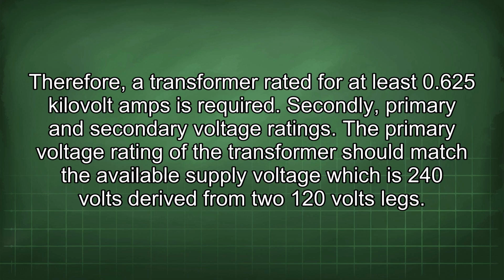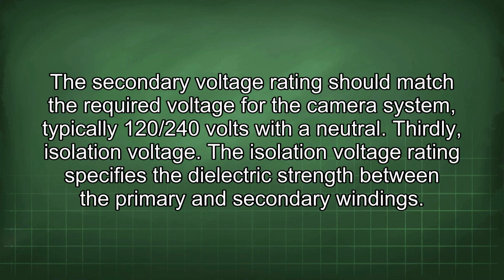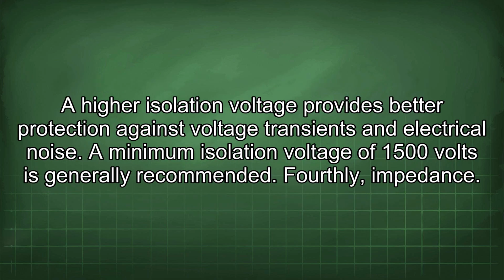Secondly, primary and secondary voltage ratings. The primary voltage rating of the transformer should match the available supply voltage, which is 240 volts derived from two 120 volts legs. The secondary voltage rating should match the required voltage for the camera system, typically 120/240 volts with a neutral. Thirdly, isolation voltage. The isolation voltage rating specifies the dielectric strength between the primary and secondary windings. A higher isolation voltage provides better protection against voltage transients and electrical noise. A minimum isolation voltage of 1500 volts is generally recommended.